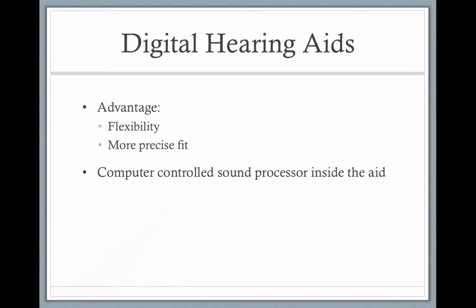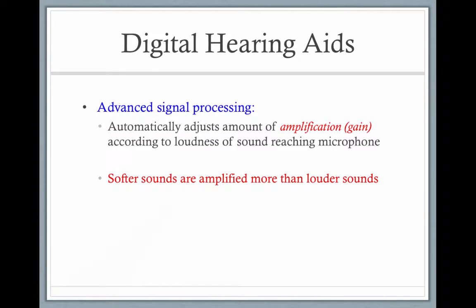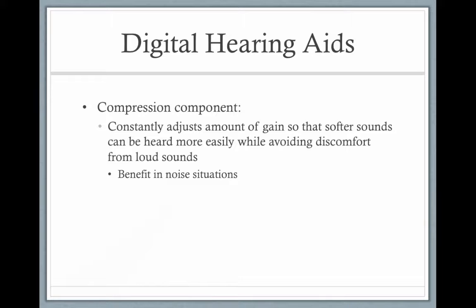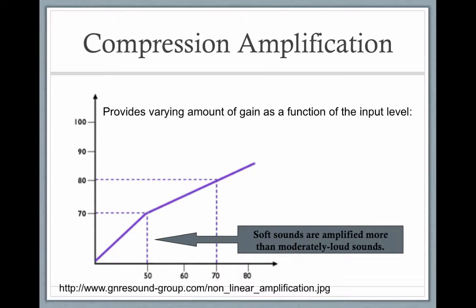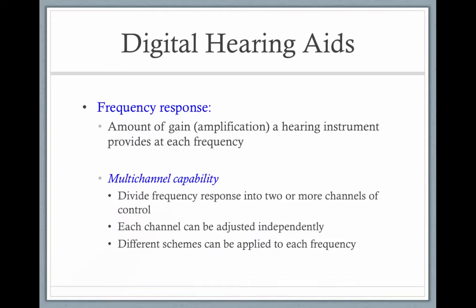Hearing aids are digital, flexible, and precise—they fit the child's needs. They have advanced signal processing that adjusts the amount of amplification, or gain. Some frequencies don't need amplification—if a child has good hearing in low frequencies, the hearing aid won't amplify those. If they need more help in high frequencies, they'll get more help there. Hearing aids also have compression circuitry, so loud sounds don't get uncomfortably loud. Soft sounds get the most amplification, moderate sounds get some, and loud sounds get none, because they're already loud enough.